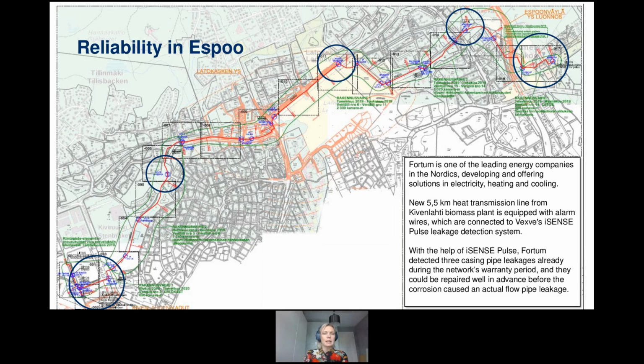On the left-hand corner, you can see their new biomass plant, and they have built a new heat transmission line of 5.5 kilometers. And this transmission line is equipped with alarm wires. On those three rounded spots in the middle, there's an iSense Pulse leak detection box underground. We are measuring in both directions so that with 3 boxes, we can cover the whole network. And during the first year of operation, our iSense Pulse could detect 3 casing pipe leakages already. And it was possible for Fortum to fix them before any severe problems happened.